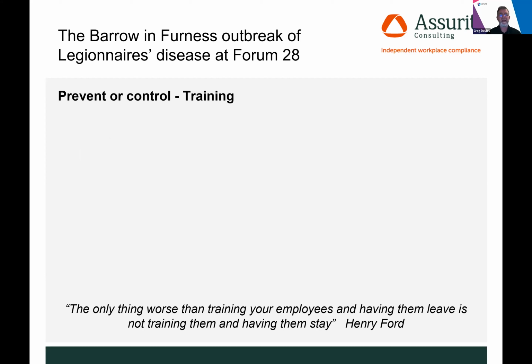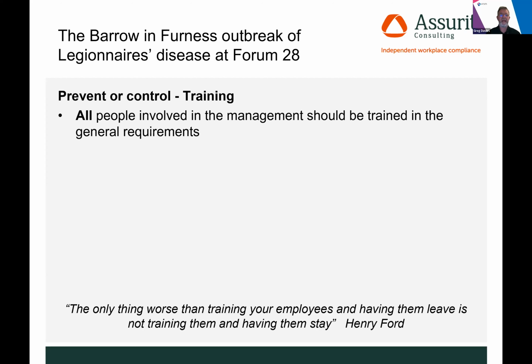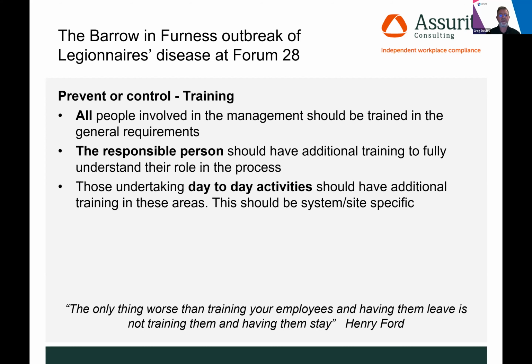With regards to training, again, this is relatively well identified in L8, in terms of ensuring that the statutory duty holder and all people involved in management should be trained in the general requirements of the subject, so understanding Legionella awareness. The responsible person, their deputy, and anyone else filling a managerial role should have some form of Legionella management training. Those undertaking day-to-day activities, possibly a combination of both, need to be competent for the tasks they're performing, whether that's a cooling tower water treatment visit, taking a sample, or for hot and cold water systems, the flushing and temperatures that need to be carried out depending on the requirements of your written scheme and the approved code of practice.